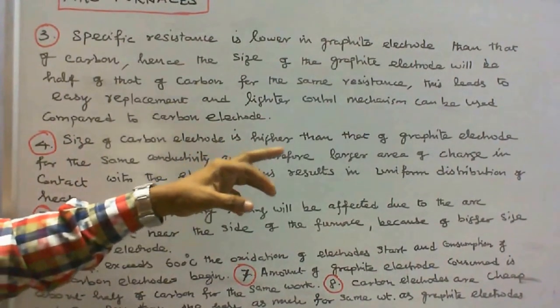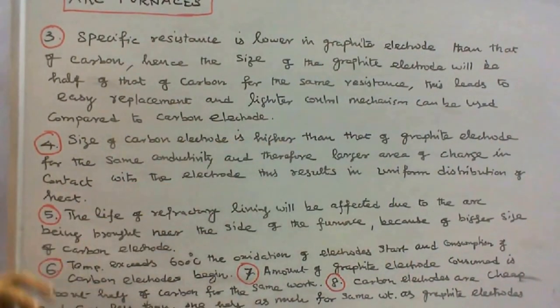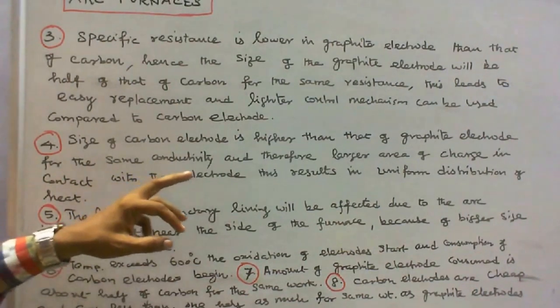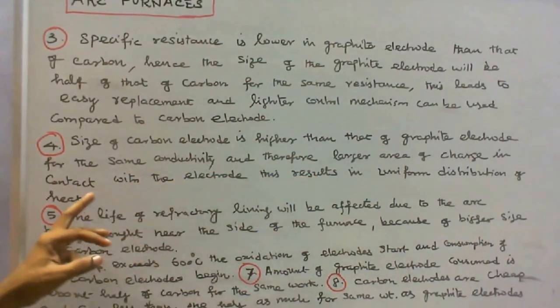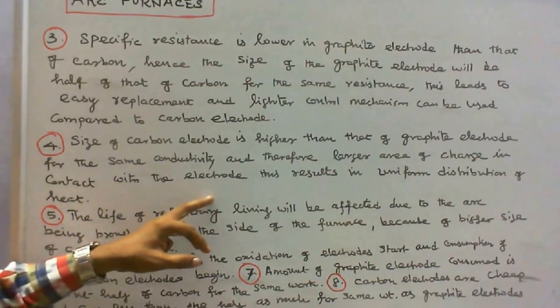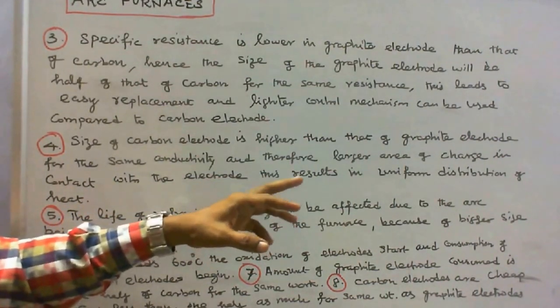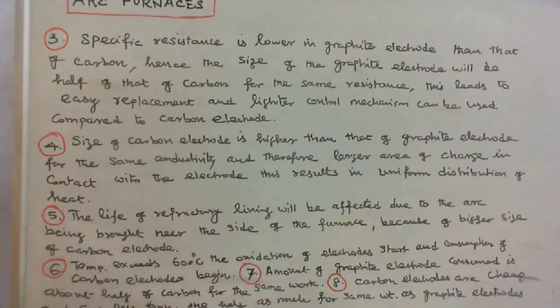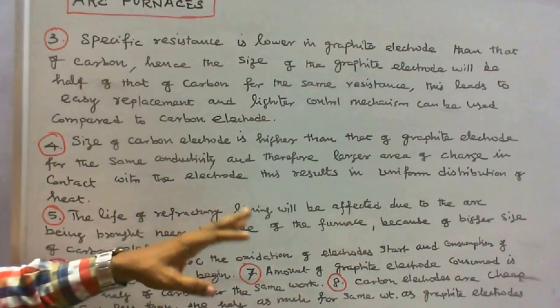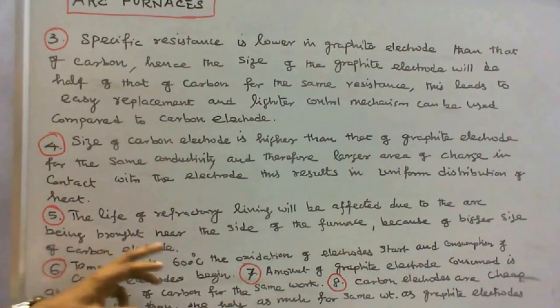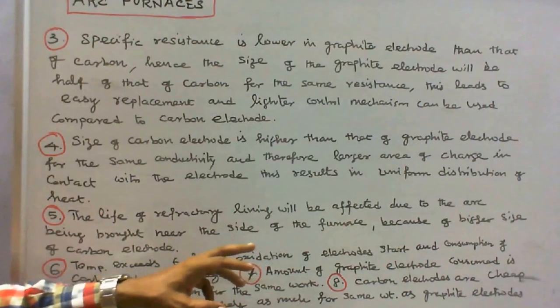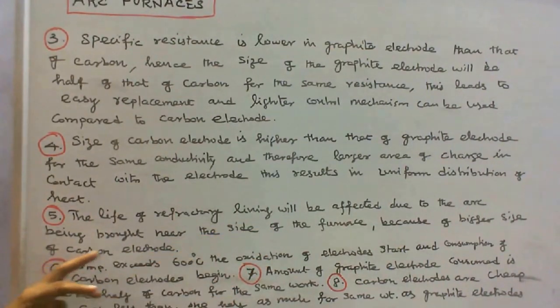Number four: size of carbon electrode is higher than that of graphite electrode for the same conductivity, and therefore larger area of charge in contact with the electrode. This results in uniform distribution of heat. Number five: the life of refractory lining will be affected due to the arc being brought near the side of the furnace because of bigger size of carbon electrode.